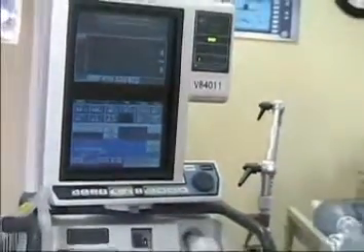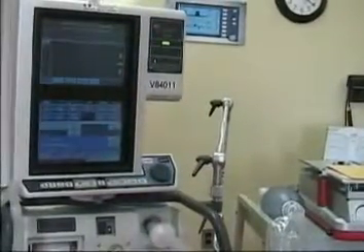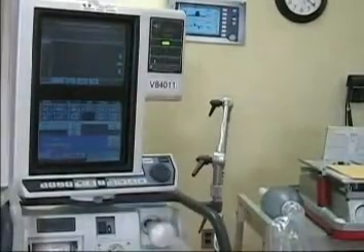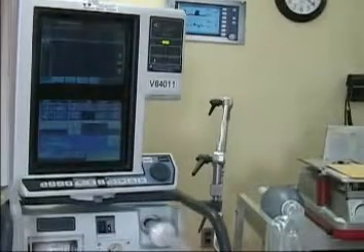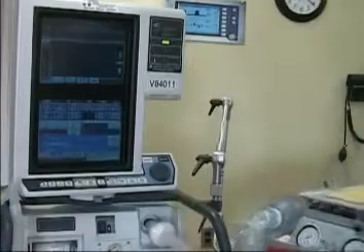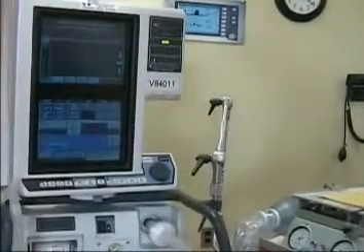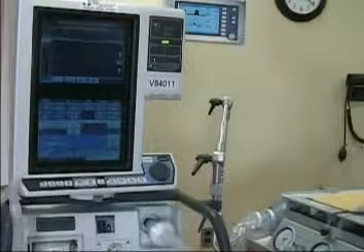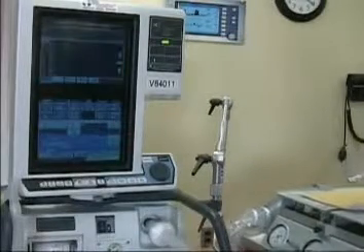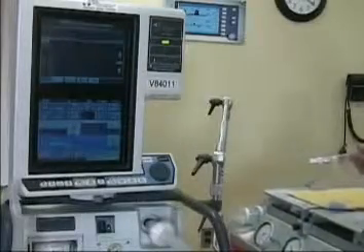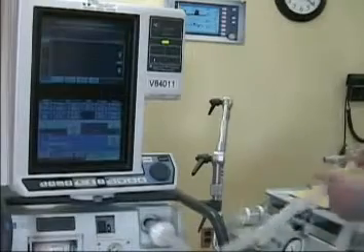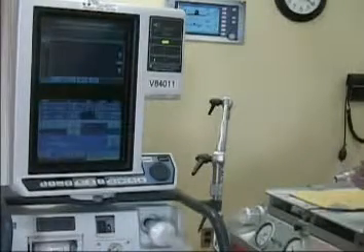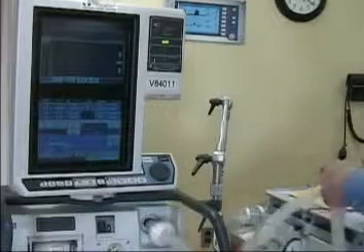This is ideal for when you have a patient coming back from surgery. Our patient arrives. I will move my test lung so that we can see it. We're going to connect the ventilator to my test lung. As soon as the ventilator is connected to the test lung, it will start ventilating.